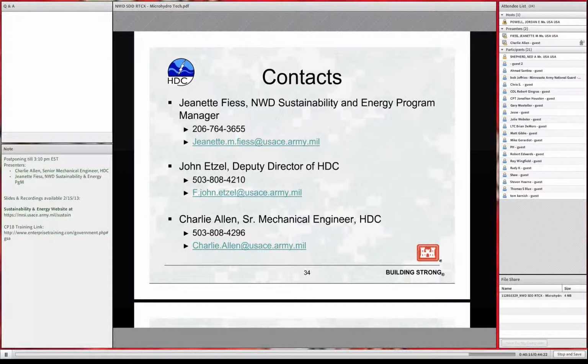Excuse me for a moment if I can break in here. When you're looking at pressure reducing valves, remember that the only energy available is the inlet pressure at the inlet to the valve minus the pressure at the outlet of the valve. Don't make the mistake of assuming you can take all of the pressure in the conduit to generate power. You can only take the amount of pressure that the PRV itself burns off as you make these calculations for the available amount of power. I'm out.